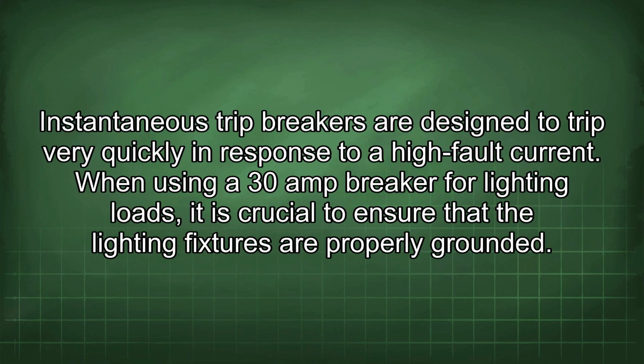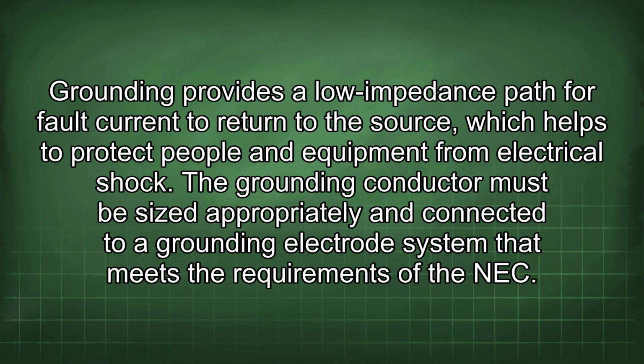Instantaneous trip breakers are designed to trip very quickly in response to a high fault current. When using a 30-amp breaker for lighting loads, it is crucial to ensure that the lighting fixtures are properly grounded. Grounding provides a low impedance path for fault current to return to the source, which helps to protect people and equipment from electrical shock. The grounding conductor must be sized appropriately and connected to a grounding electrode system that meets the requirements of the NEC.